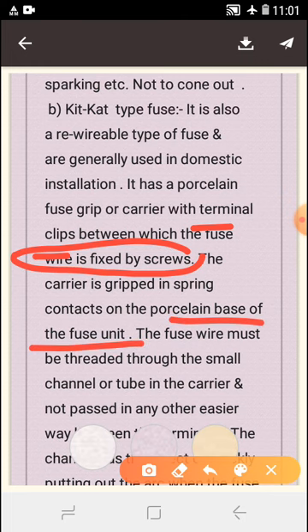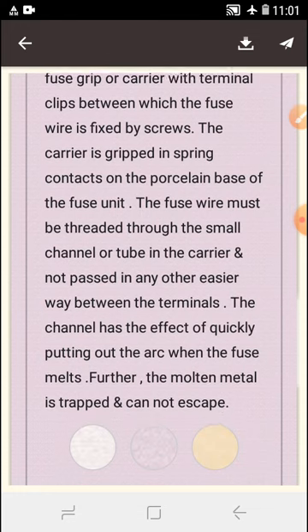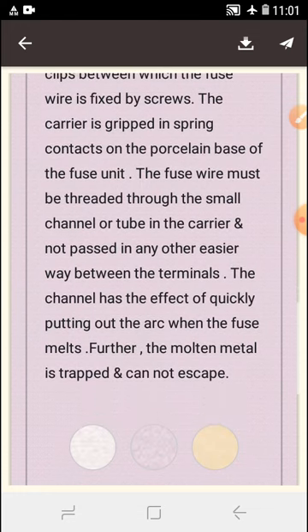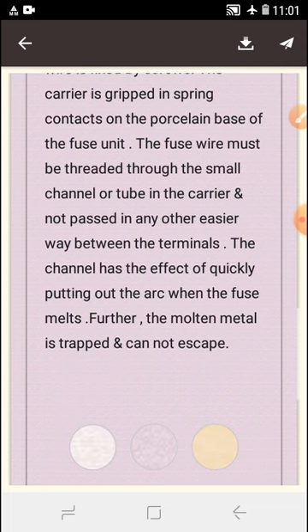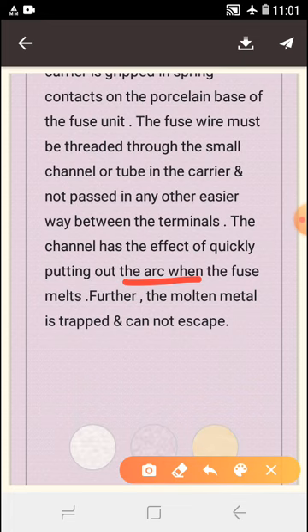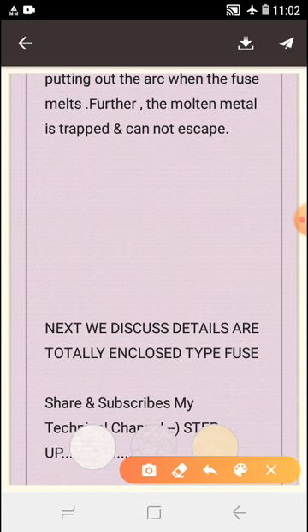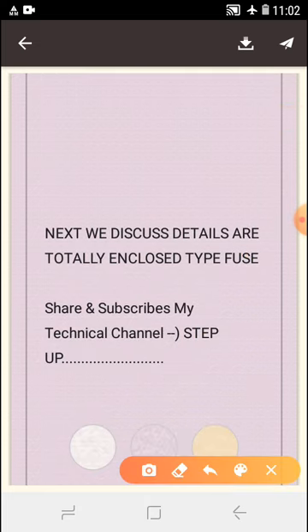The fuse wire must be threaded through the small channel or tube in the carrier and not pass any other way between the terminals. The channel has the effect of quickly putting out the arc when the fuse melts, and the molten metal is contained and cannot escape. Next we will discuss totally enclosed type fuse in detail.